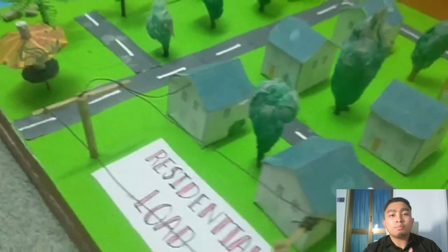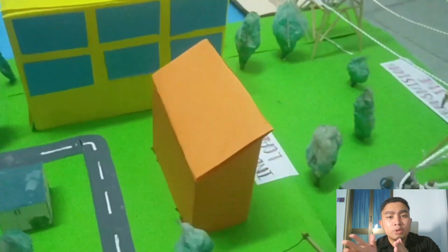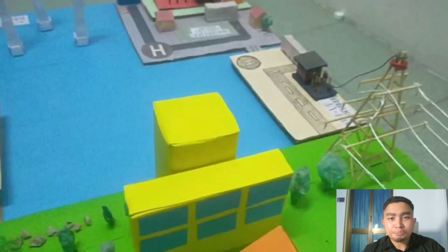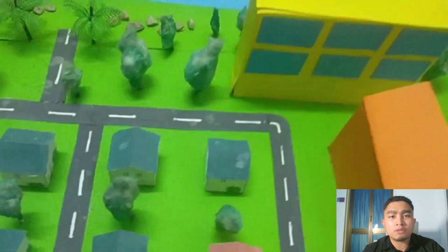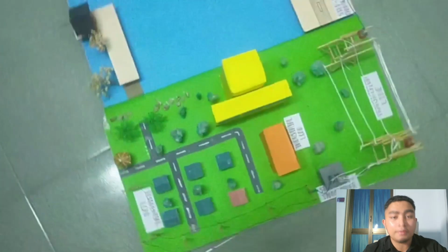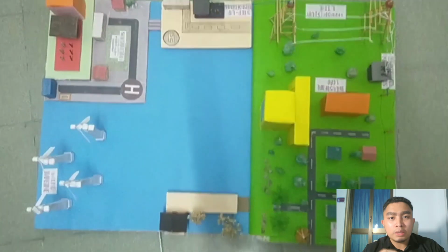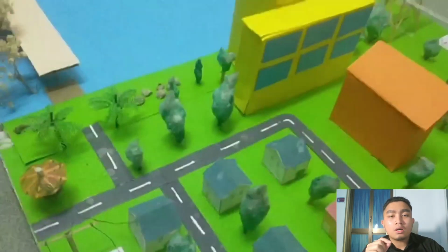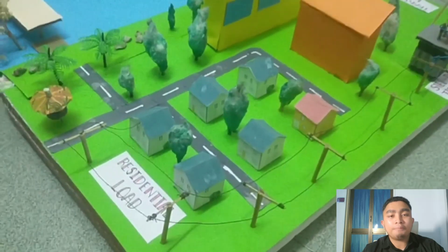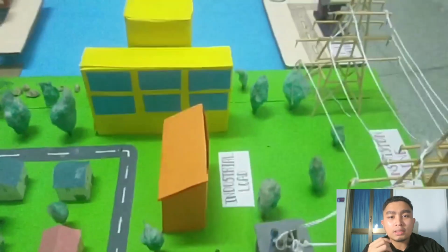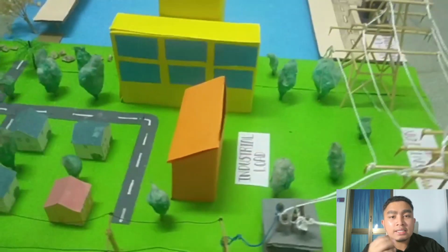The function of both the switchgear and transformer on site is for further control and also to distribute the stepped down voltage to certain parts of the industrial section. And for your information, in Malaysia, usually we use about 440 volts for a 3-phase system in the industrial section. For machinery and equipment, we use about 400 volts between phases and 230 volts between each phase and the neutral line. Also, in Malaysia, large industries usually have their own substation in order to ensure that the supply is uninterrupted.